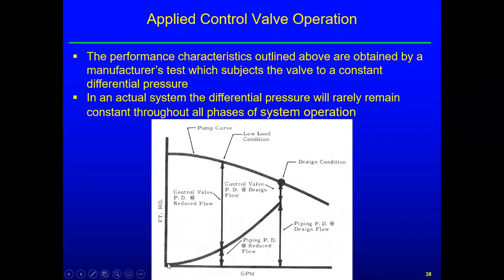The bottom curve, which sweeps up from 0, 0, kind of the parabolic looking curve, is the system curve. And so that represents the piping pressure drop as a function of flow. And you can see it's roughly a second order curve. And as the GPM goes up, that's the frictional loss to push the water through the pipes and the fittings and all of that. So really that's everything in the system except the control valve. You can draw that system curve to include the control valve and have just one smooth curve.